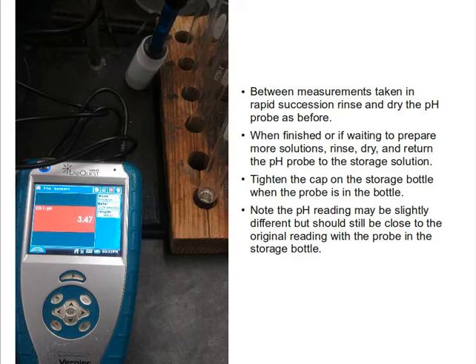When making several measurements in rapid succession, simply rinse and dry the probe as before. When finished or stopping to prepare more solutions, rinse, dry, and place the probe into the storage solution bottle with the cap tightened. The same probe handling instructions should be followed for each part of the procedure.